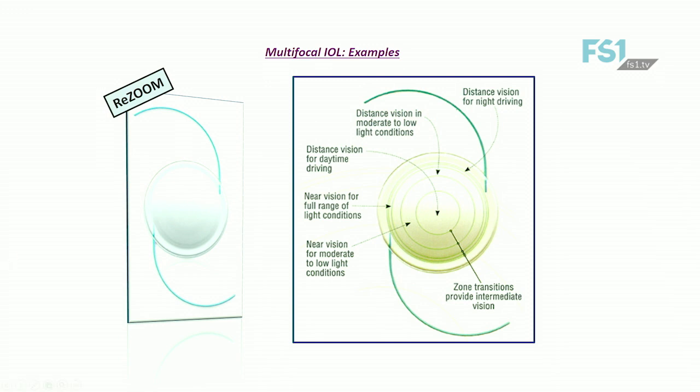In bright conditions, when the pupil is small, the lens is distance dominant. As the pupil gets larger, the near distance focus is being attenuated. When someone is driving a car in normal light, the IOL provides good distance focus, but during reading in bright light, the small pupil provides poor near vision, and the lens provides good intermediate and distance vision.